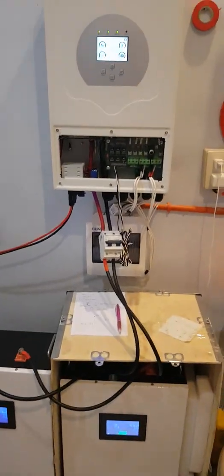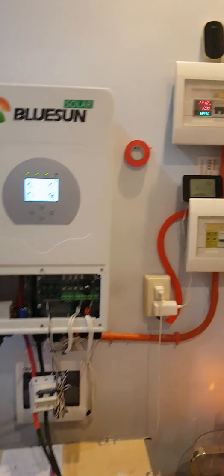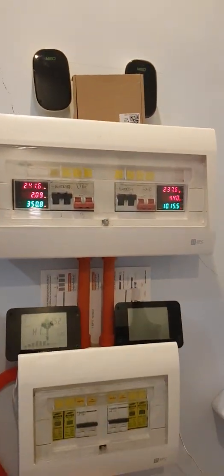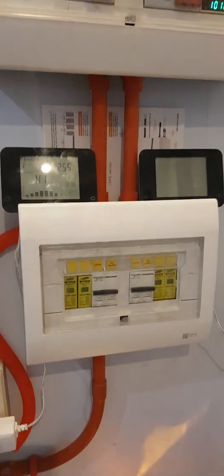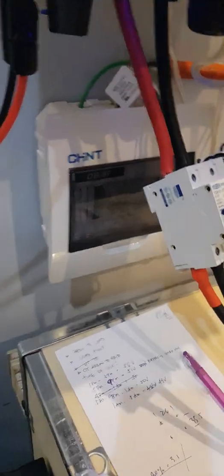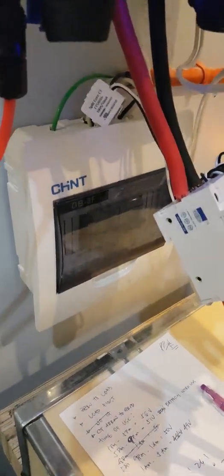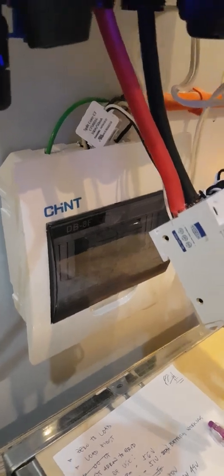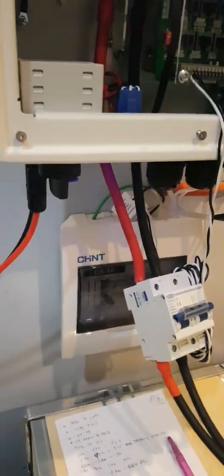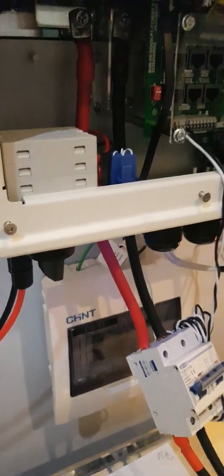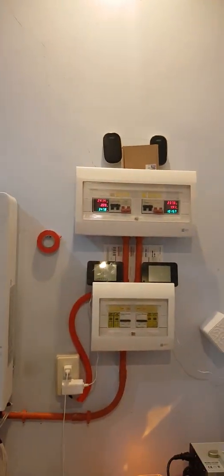So this is the Deye setup for my system. This is a test run for the inverter, the batteries, and my controls. This is the circuit breakers with SPD. This is the circuit breaker for the battery, and just an additional circuit breaker for easy access. And if I want to do testing, I can easily shut down using this circuit breaker. So I will do more videos next time.